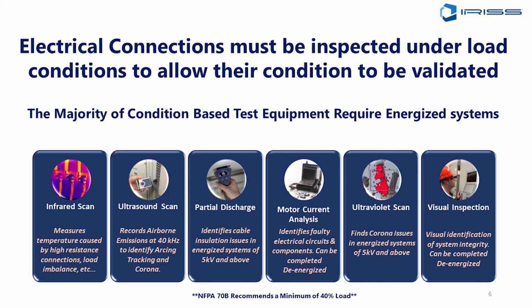And lastly, we should never discount our senses. All 5, right? When I visually inspect a piece of equipment, what am I looking for? I'm looking for signs of water ingress. I'm looking for dust accumulation. I'm looking for pests that may have gotten in, snakes, spiders, all kinds of other critters like warm places that electrical enclosures provide. I am also smelling the equipment. Is there an unusual smell coming off of it, that burning insulation smell or anything else that's strange? The smell of ozone, that smell you get after a lightning storm, right? That's something we can pick up with our senses. Some people are more in tune to it than others.